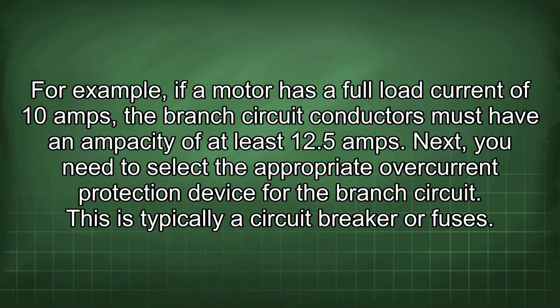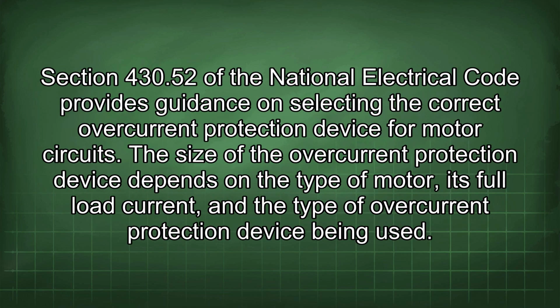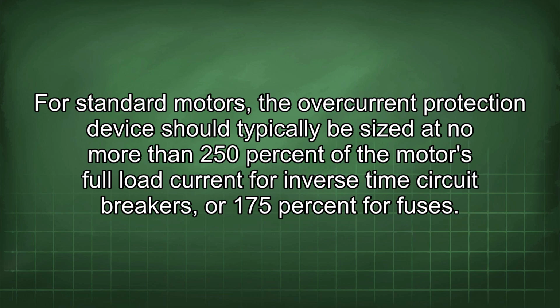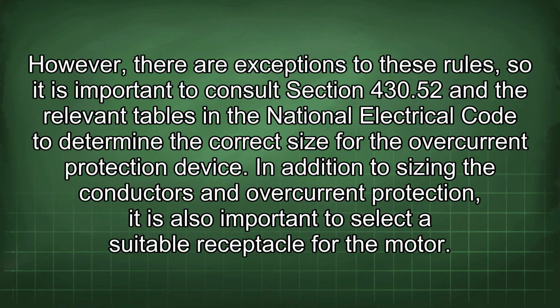Next, you need to select the appropriate overcurrent protection device for the branch circuit. This is typically a circuit breaker or fuses. Section 430.52 of the National Electrical Code provides guidance on selecting the correct overcurrent protection device for motor circuits. The size of the overcurrent protection device depends on the type of motor, its full load current, and the type of overcurrent protection device being used. For standard motors, the overcurrent protection device should typically be sized at no more than 250% of the motor's full load current for inverse time circuit breakers, or 175% for fuses. However, there are exceptions to these rules, so it is important to consult Section 430.52 and the relevant tables in the National Electrical Code to determine the correct size for the overcurrent protection device.